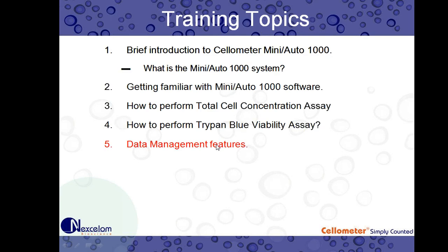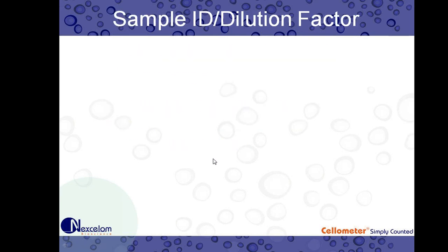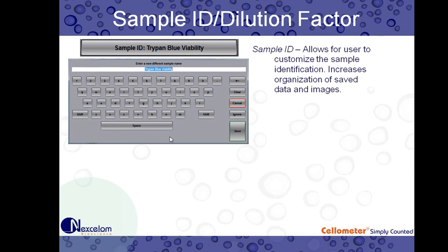So let's go over some of the data management options we have available on our Auto 1000 and Mini. So I went over the sample ID and dilution factor. The sample ID, it allows for users to customize the sample identification. This increases the organization of saved data and images. So when you go back and look at your USB drive or your network drive where all your data and images are saved, it allows you to easily recall what cell sample you may have counted. You can enter in a dilution factor. You can enter in, you know, custom...